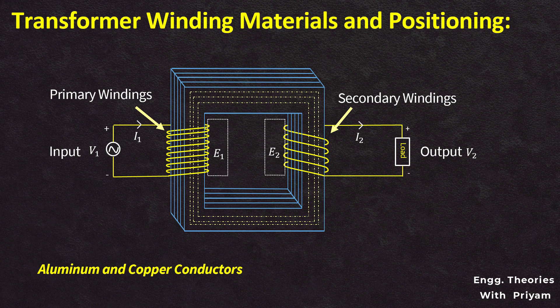In terms of insulation requirements, the position of higher voltage HV and LV windings with respect to the core is very critical. It would be essential to insulate the HV winding from both the core and the LV winding if it were located near to the core. Furthermore, two layers of high voltage insulation would be necessary. When the high voltage winding is placed outside and around the low voltage winding, only one layer of high voltage insulation is necessary.